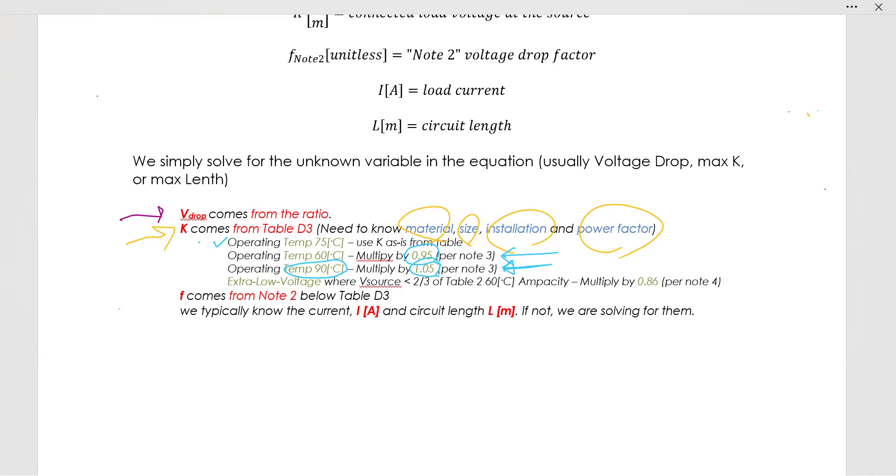If the voltage drop came from a ratio, K came from Table D3. If the temperature is 75 degrees, we keep it as it was from the table. If we're at operating temperature 60 degrees, multiply by 0.95. If it's 90 degrees, multiply by 1.05. And if it is extra low voltage, defined by the voltage source being less than two-thirds of table 2 60 degree Celsius capacity, then you multiply by 0.86. That is in note 4.